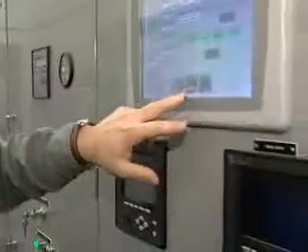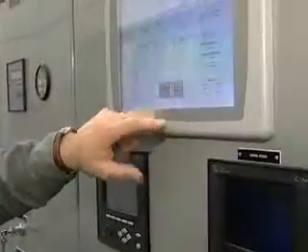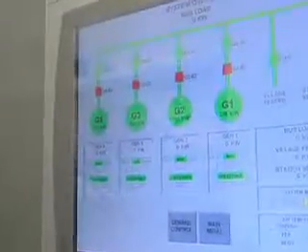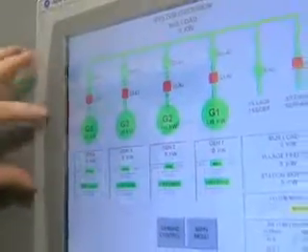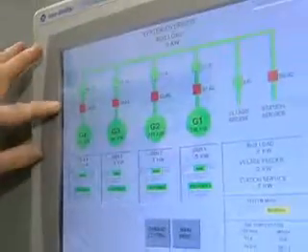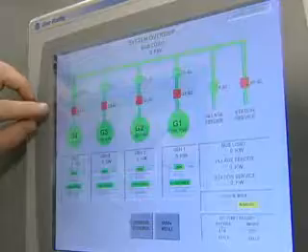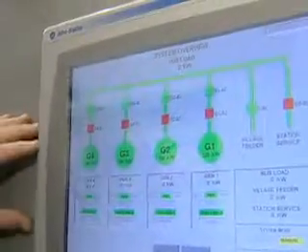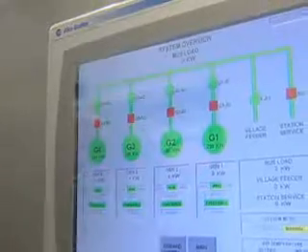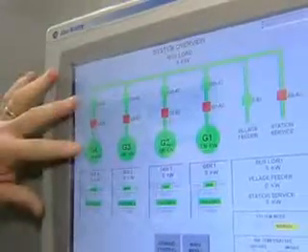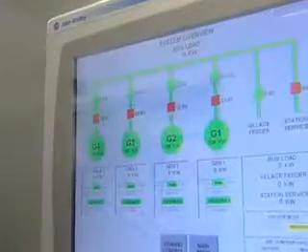We have a couple other screens. The system overview basically tells us: green means the system is down and not running right now. Red — like on here — these are the circuit breakers for each engine, and red means they're closed and ready to run. Once you start an engine up, these go from green to red, meaning that engine is actually running.